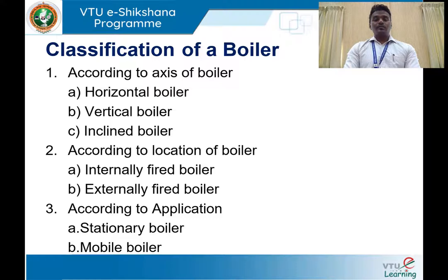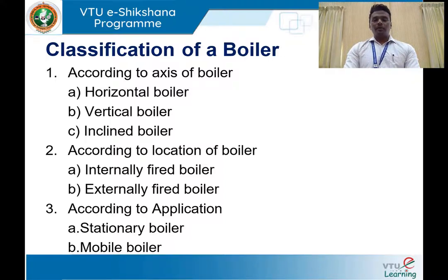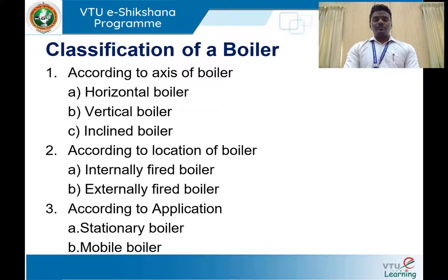Based on the location of the furnace, a boiler can be internally fired or externally fired. In order to generate steam, we need heat obtained by burning fuel in a furnace. If the furnace is a part of the boiler shell, it is an internally fired boiler. For example, in the Lancashire boiler, the furnace is part of the flue tubes inside the boiler shell. In the case of an externally fired boiler, the furnace is not part of the boiler shell — it is kept outside. In the Babcock and Wilcox boiler, combustion of fuel takes place outside the boiler shell, making it an externally fired boiler.